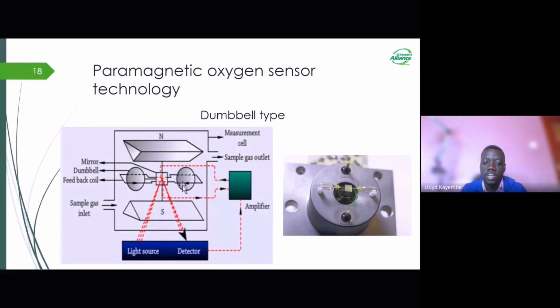So this movement causes the reflected light to move also, and then this is detected by the photocells, and the signal is then sent out to the amplifier. So then the current is generated onto the feedback coils in order to compensate this movement of the suspension. The current that is being generated is proportional to the oxygen concentration in the sensor cell. So the higher the oxygen concentration, the more the dumbbells are deflected, and the more current needs to be sent to the coils, hence detecting higher concentration using this current.